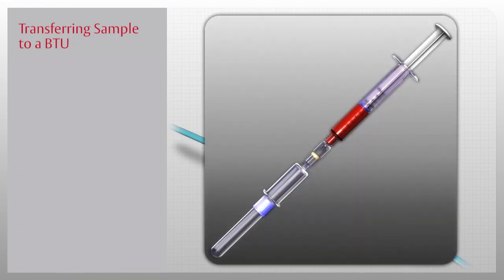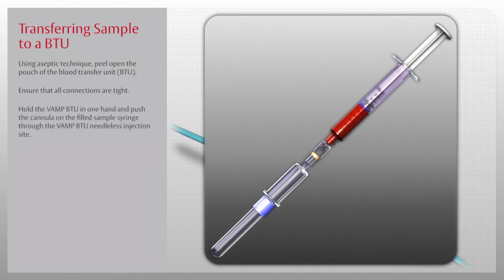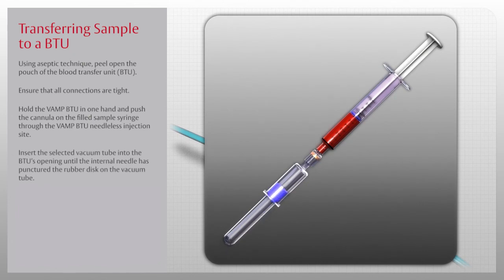To transfer the blood sample from the syringe to vacuum tubes, use the blood transfer unit, or BTU. Using aseptic technique, peel open the pouch of the BTU. Ensure that all connections are tight. Hold the VAMP BTU in one hand and push the cannula on the filled sample syringe through the VAMP BTU needleless injection site. Insert the selected vacuum tube into the BTU's opening until the internal needle has punctured the rubber disc on the vacuum tube.